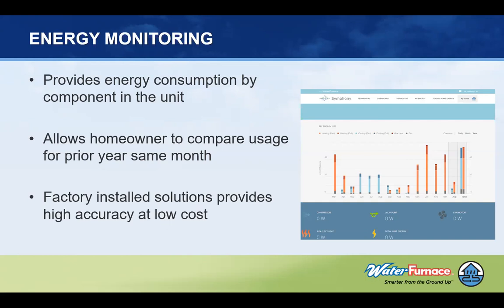And by doing this as a factory installed option, it provides a high level of accuracy at a lower cost because we can implement it for the consumer without having to measure at the 240 volt level. We know from a transformer what the turn down ratio of the voltage coming in is, and we can measure it at a 24 volt level and give you much better accuracy at a lower cost.